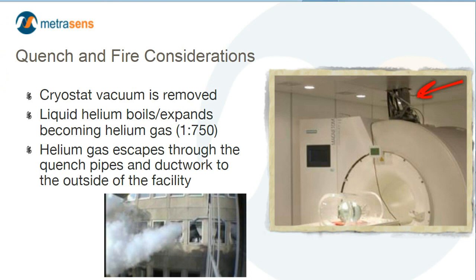Let's now move on to the subject of a magnet quench. Helium is not stable as a liquid. In order to maintain its liquid state, helium must be at a temperature of at most 4 Kelvin, which is approximately minus 452.47 degrees Fahrenheit. In order to maintain that low a temperature, the vessel or cryostat within the magnet that contains the magnet coils and the liquid helium must be vacuum sealed. If the vacuum were to be removed, the temperature within the cryostat is going to rise. Helium will boil at 4.2 Kelvin — approximately minus 452.11 degrees Fahrenheit — and it's going to expand at a ratio of approximately 1 to 750. This means for one liter of liquid helium, it would expand to approximately 750 liters of helium gas.